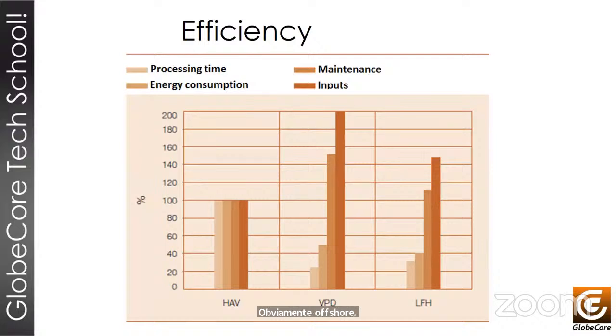This graphic chart shows a comparable table for the methods of drying the insulation in vacuum ovens. HAV is the method of drying through hot air blowing followed by a cycle of vacuuming. VPD is a method of drying by means of solvent vapors, and LFH is a method of drying through low-frequency currents. The HAV method requires expenditures in terms of processing time and energy consumption. Considering that the hot air blowing unit can reach a power level over 100 kilowatts per hour, it takes much more time compared to advanced methods of drying.